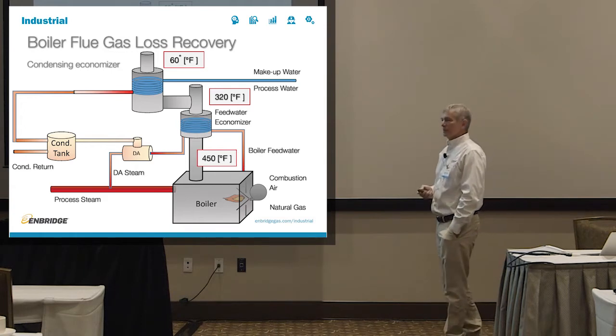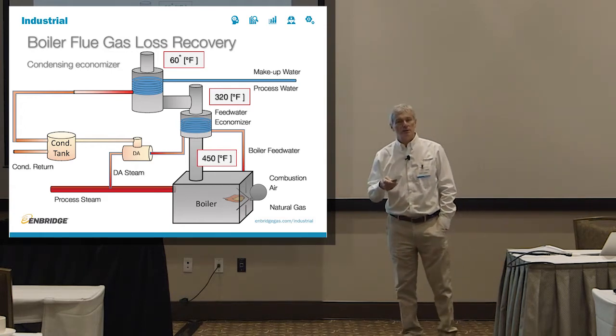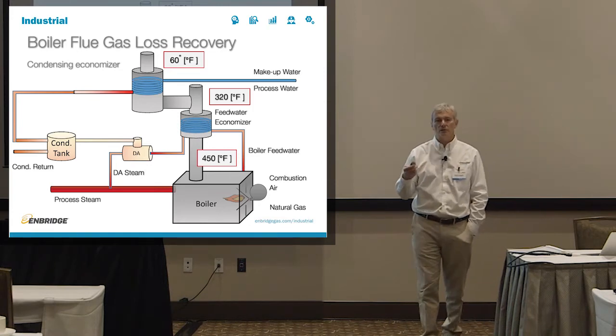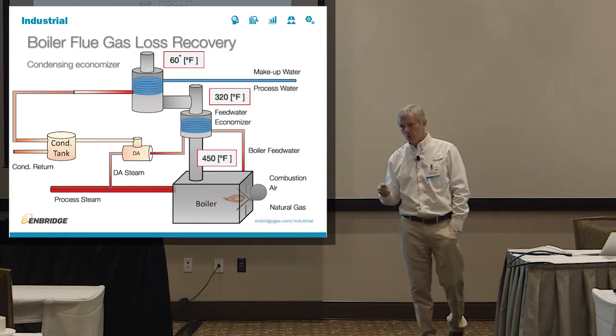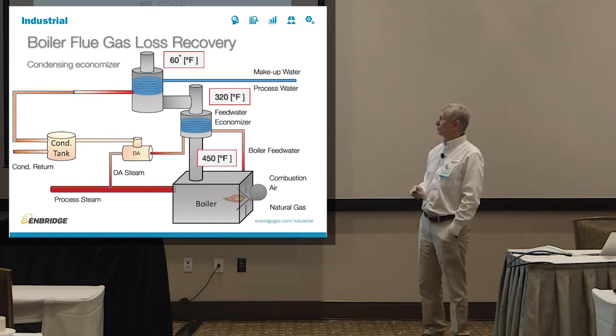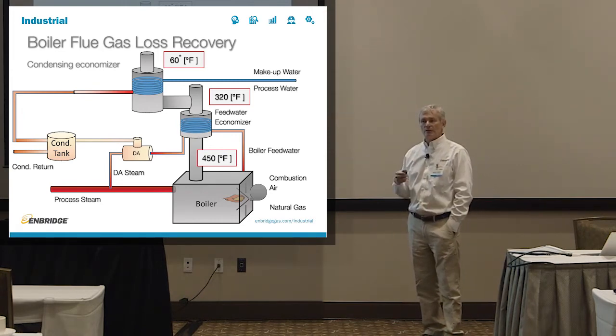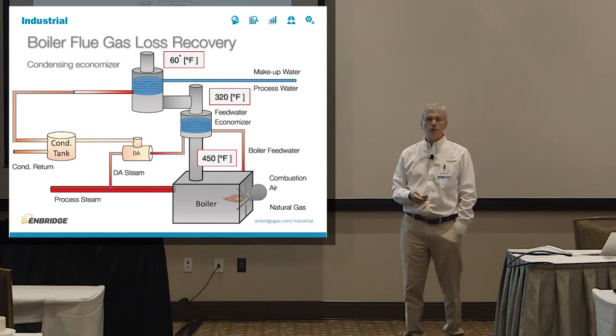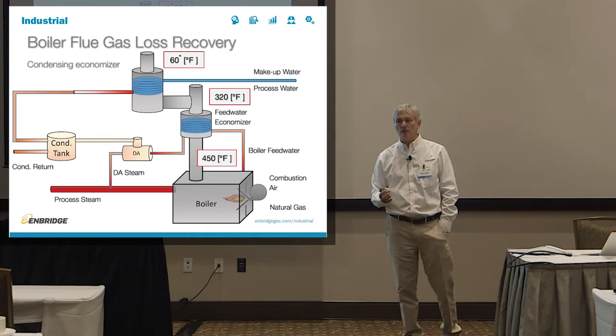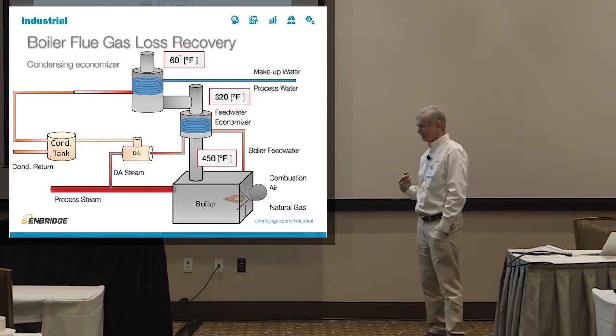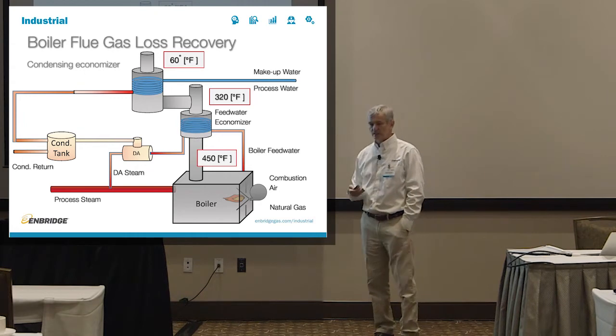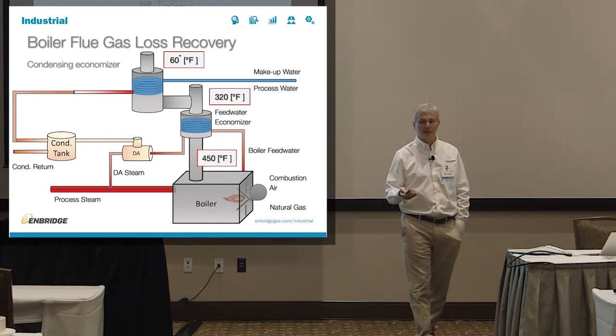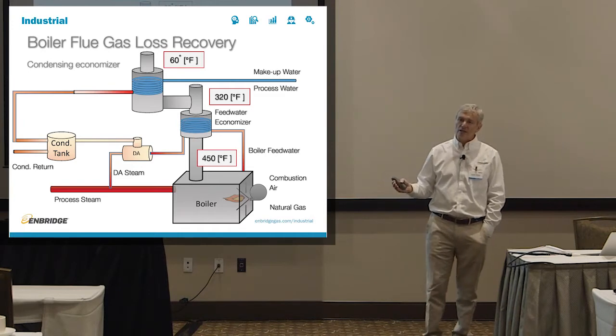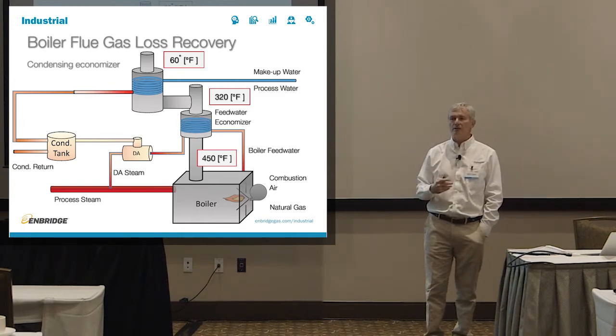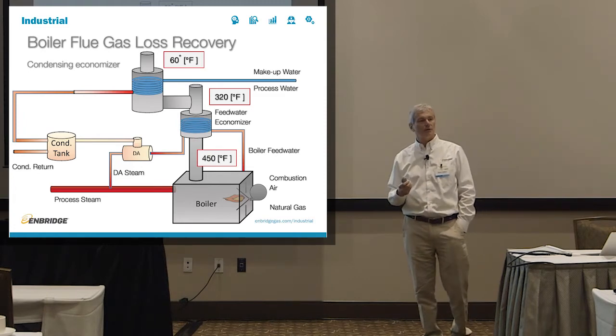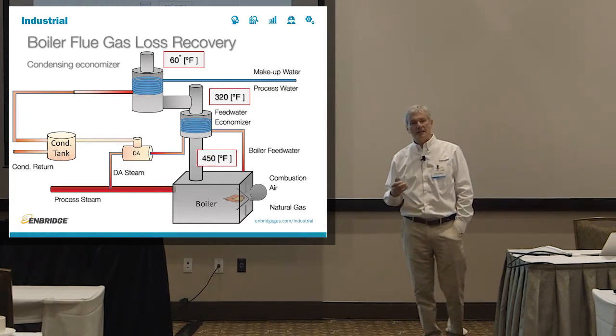The other thing that I really like about the condensing economizer is for everybody who's using process water, who's preheating a large and constant amount of process water, and you have a boiler, I would always advise using a condensing economizer for the process water stream. It's one of the easiest ways to preheat the water, and it reduces your energy use in water heating tremendously. In my personal experience, we had a customer installing an economizer that didn't have a feed water economizer, and we installed a condensing economizer directly onto the unit. We didn't even bother with the feed water economizer because the process water amount that they had was phenomenal and they used all of it.